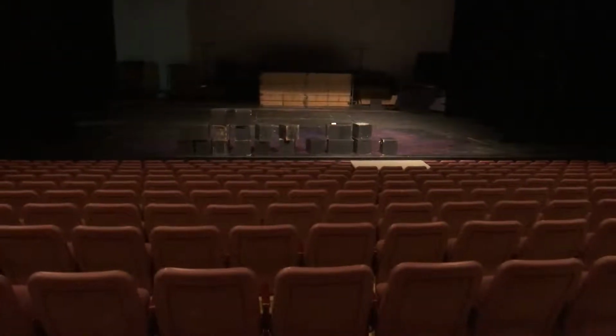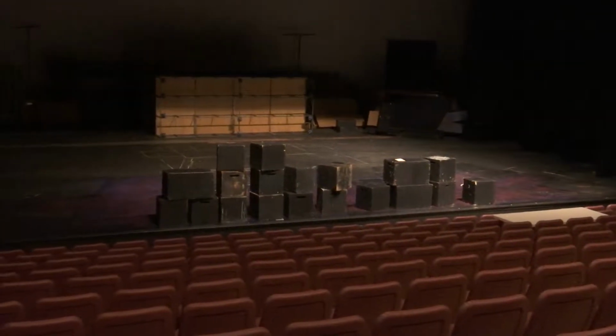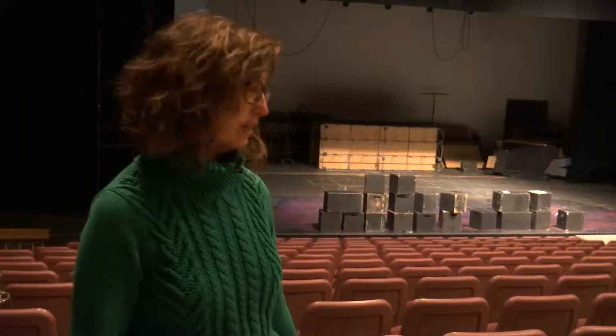Here we're in the theater. The theater is in unoccupied mode right now. You could hear that there's nothing running. A big part of energy audits is listening and hearing, whether you hear fans running, and looking, I guess, to see if there's lights on anywhere, and making sure everything's quiet and dark.